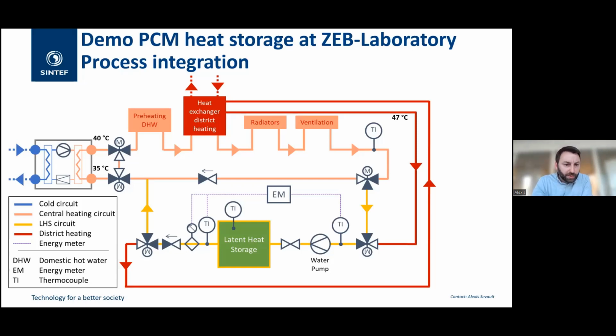We look only at the hot side of the heat pump. The regular loop sends water at 40 degrees to the preheating of the domestic hot water, then to the radiators, and then to the ventilation air, where there's a heat exchanger, and then it returns to the heat pump at 35 degrees once these consumers have used what they want. We can have a little top-up from the district heating on the way - that's the red box - to this system. And when it's very cold, the water will come back at a lower temperature than 35. So we can support the heat pump a bit there.